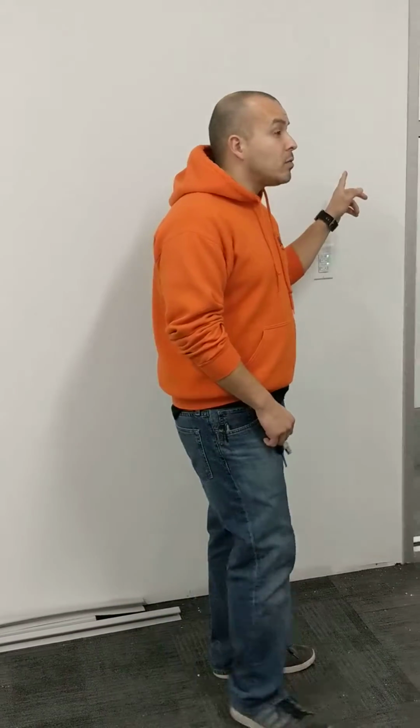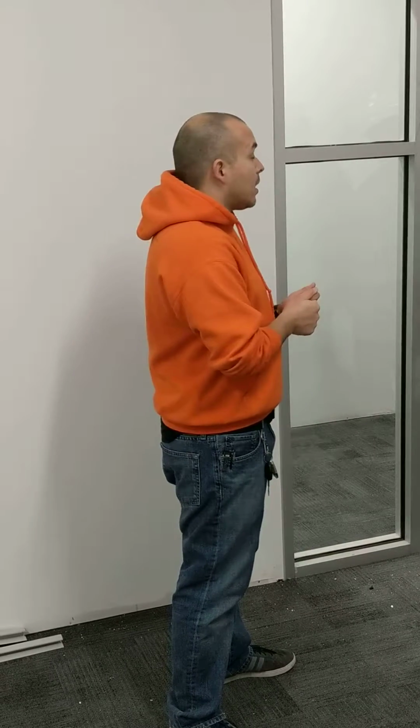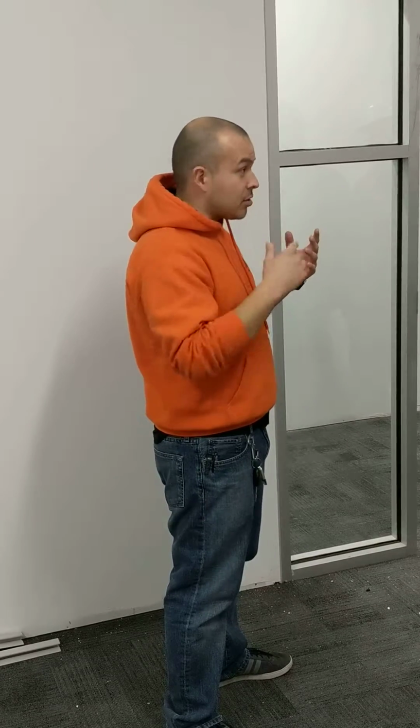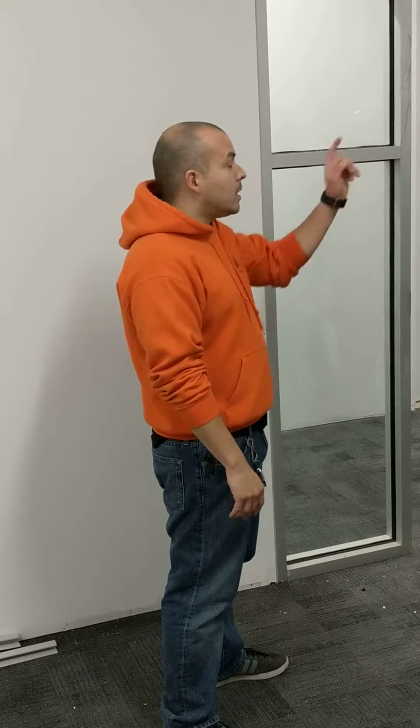Similarly, bathrooms and your main lobby-way are standalone systems. They're gonna be set up for, I believe, 10 minutes default for the bathrooms. And those are gonna be automatic on, automatic off. So restrooms do have an exemption with the code. Again, if they turn off on somebody, if they scream hey, because they're in the middle of a stall and it just happens to be an extended visit, the lights will go ahead and turn back on for them in that 15-second window. And then your main lobby, it's exempt as well. So again, anybody walking in and out, it's always gonna turn on.